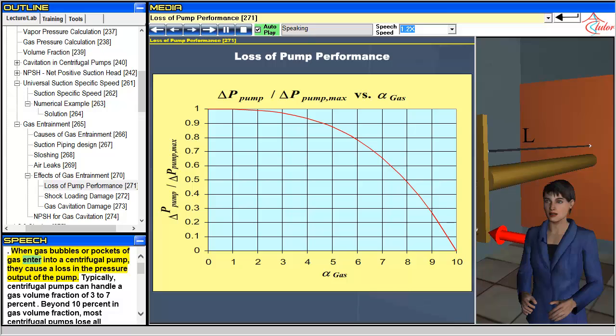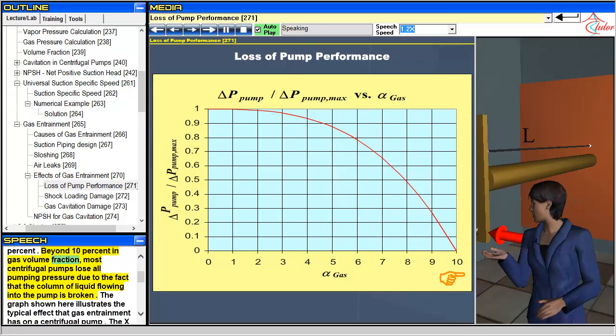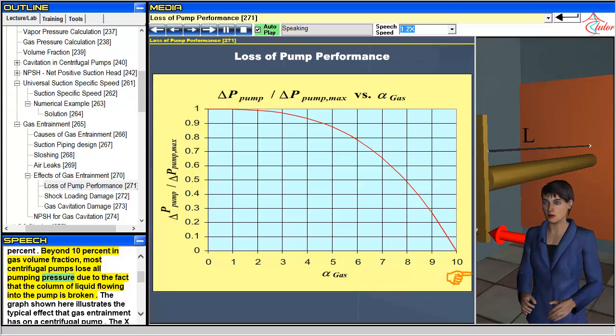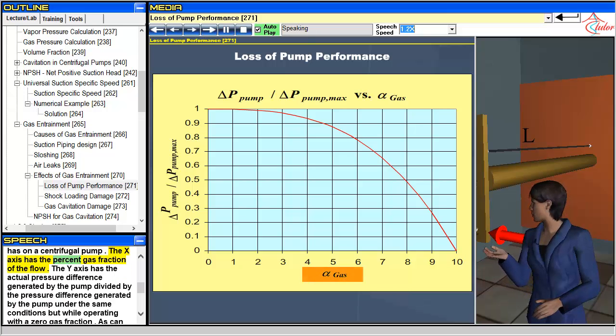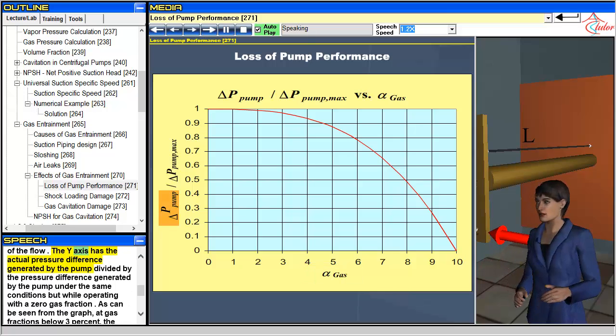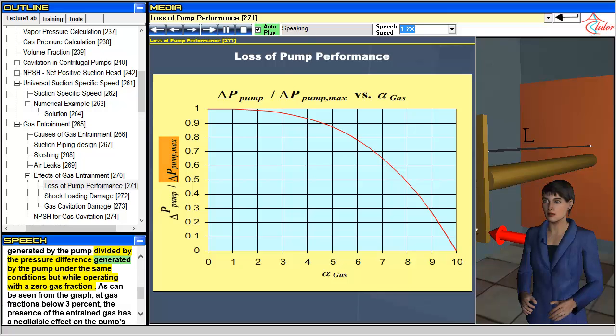When gas bubbles or pockets of gas enter into a centrifugal pump, they cause a loss in the pressure output of the pump. Typically, centrifugal pumps can handle a gas volume fraction of 3 to 7 percent. Beyond 10 percent gas volume fraction, most centrifugal pumps lose all pumping pressure due to the fact that the column of liquid flowing into the pump is broken. The graph shown here illustrates the typical effect that gas entrainment has on a centrifugal pump. The x-axis has the percent gas fraction of the flow, and the y-axis has the actual pressure difference generated by the pump, divided by the pressure difference generated by the pump under the same conditions but while operating with a zero gas fraction.